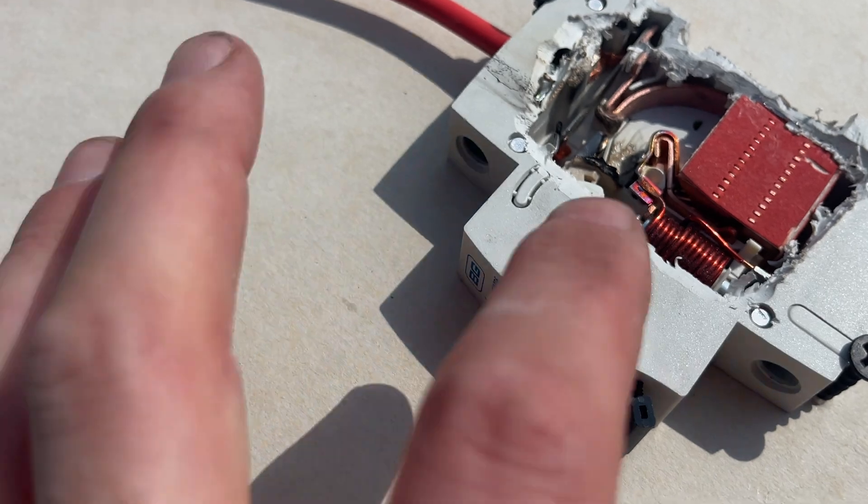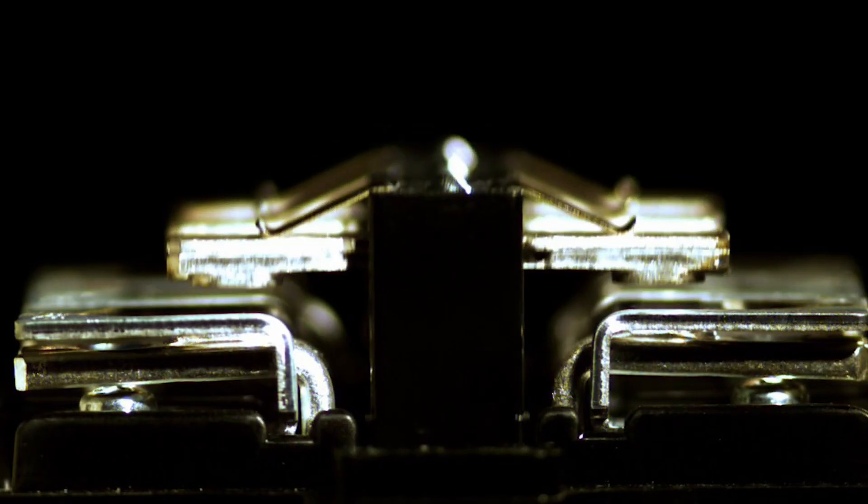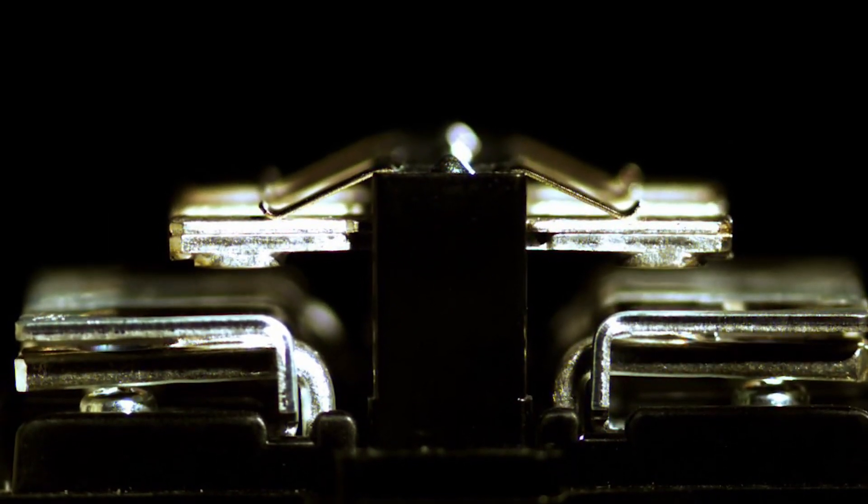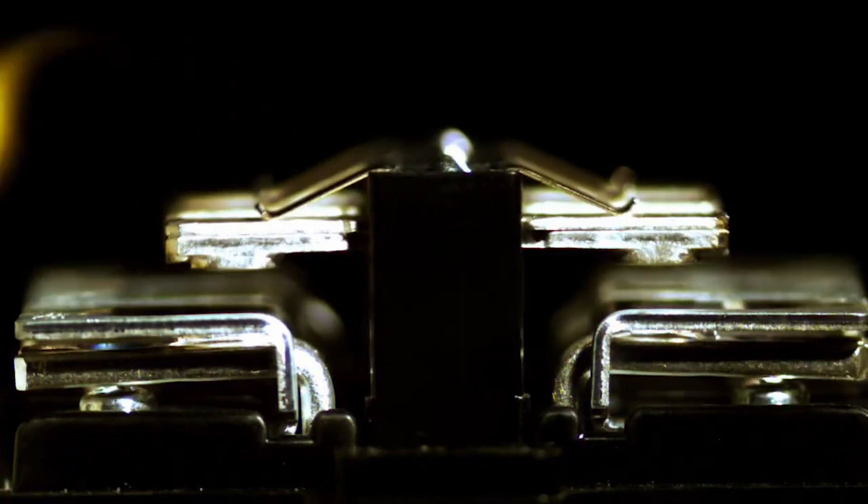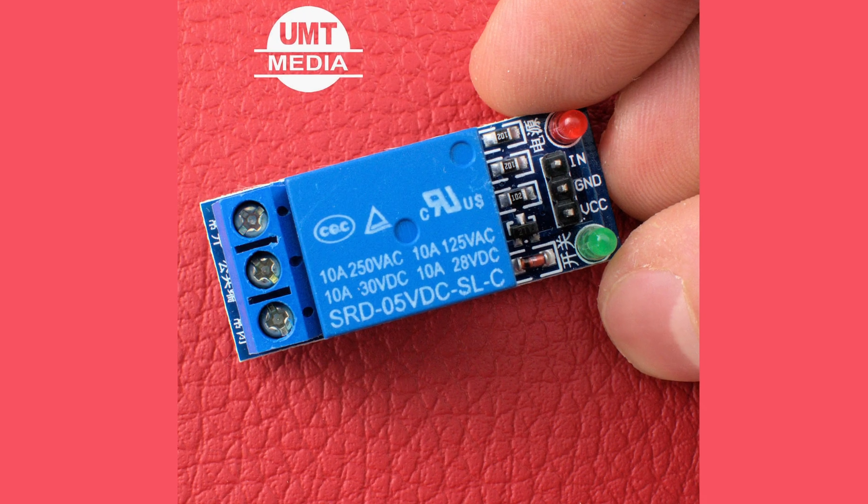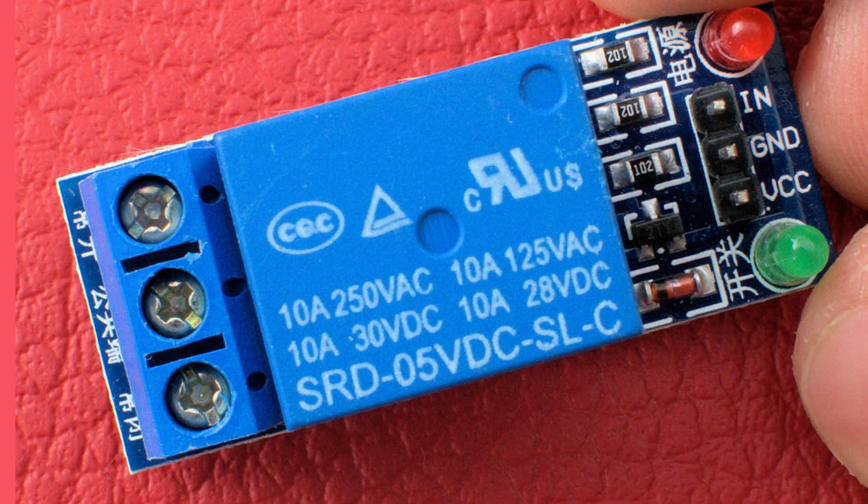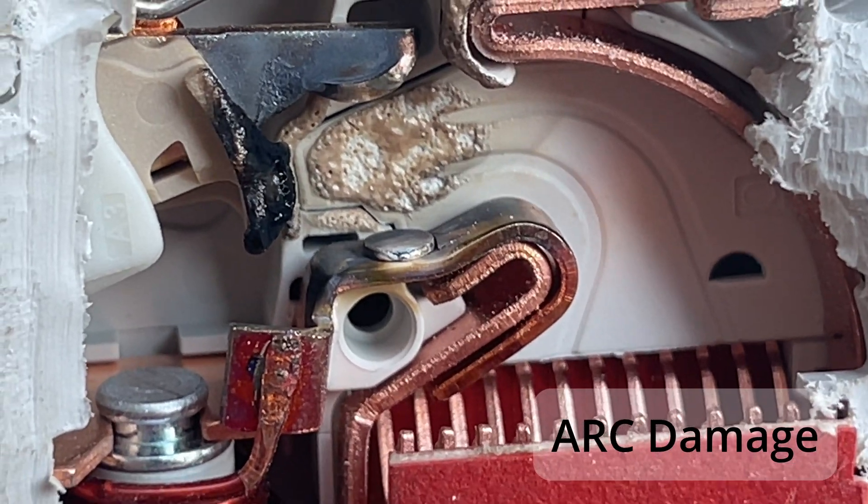The same process goes for not just MCBs, but any sort of connection device that's designed to break a circuit, so maybe relays or isolators. You'll find that quite often a relay can have a DC rating, but it's often a lot, lot lower than what you'd expect for AC and it's all down to this breaking the contact.